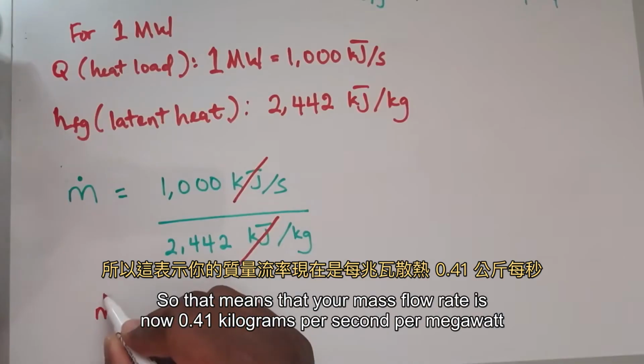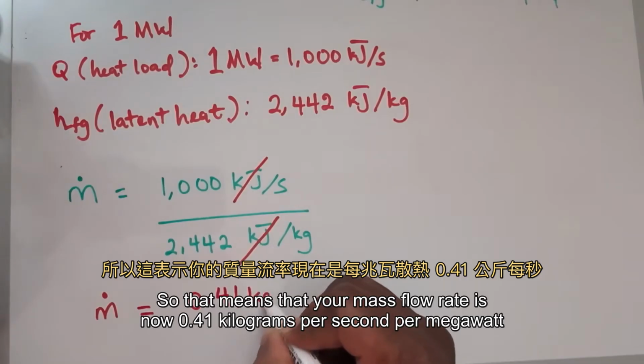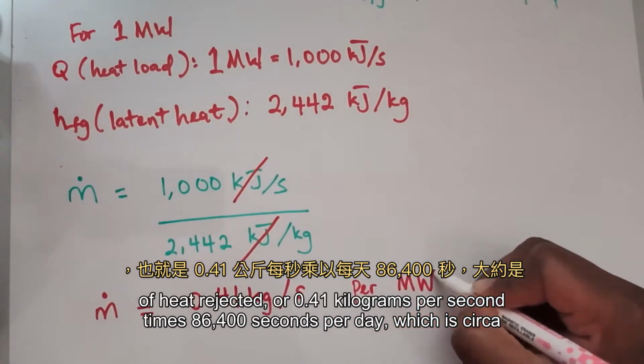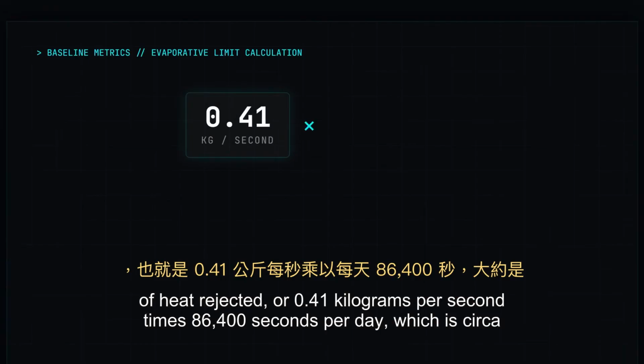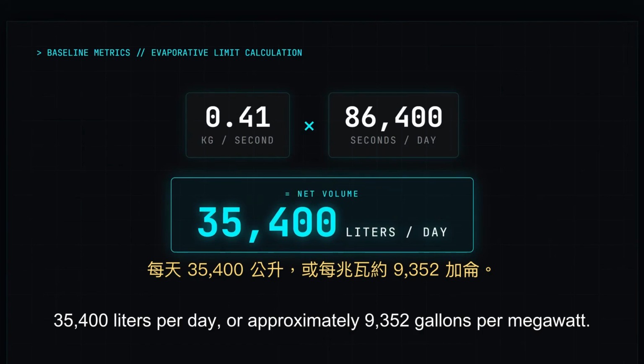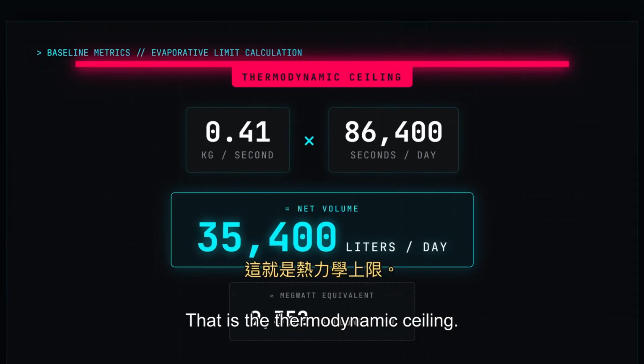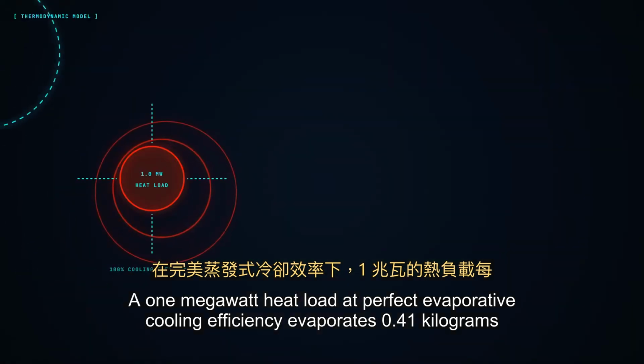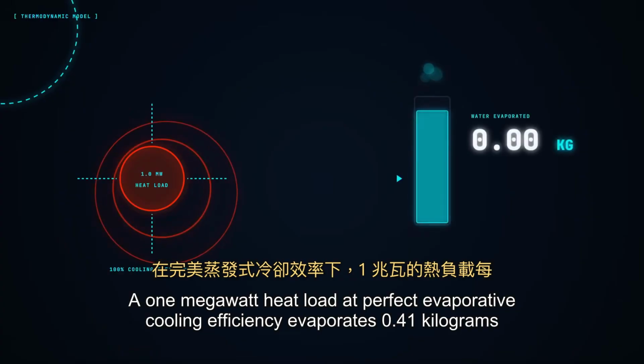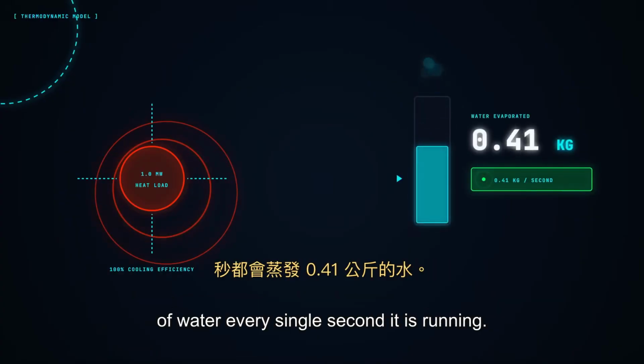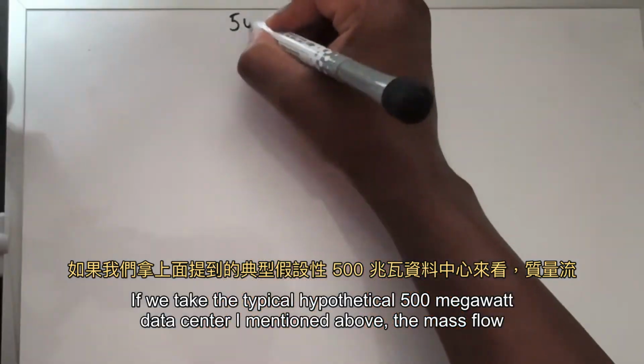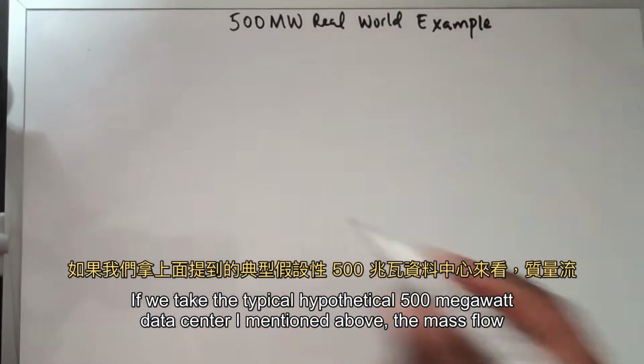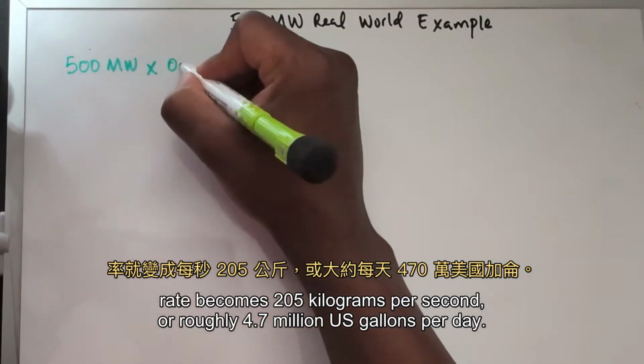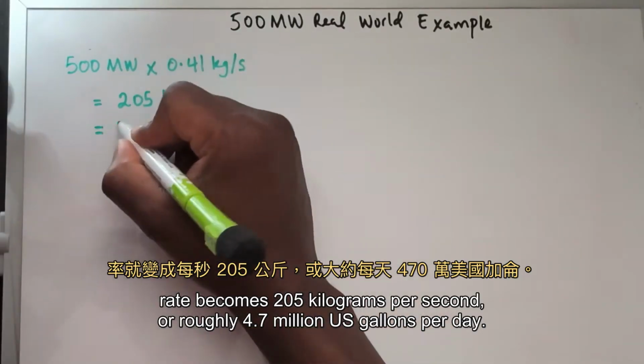So that means that your mass flow rate is now 0.41 kilograms per second per megawatt of heat rejected, or 0.41 kilogram per second times 86,400 seconds per day, which is circa 35,400 liters per day, or approximately 9,352 gallons per megawatt. That is the thermodynamic ceiling. A 1 megawatt heat load at perfect evaporative cooling efficiency evaporates 0.41 kilograms of water every single second it is running. If we take the typical hypothetical 500 megawatt data center I mentioned above, the mass flow rate becomes 205 kilograms per second, or roughly 4.7 million US gallons per day.